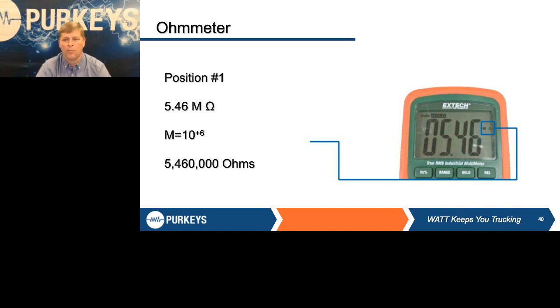So that is not 5.46 ohms, that is 5,460,000 ohms. Is that more than 6K? Yes. A lot of times those service manuals, all they're asking for is some sort of what they consider an infinite reading, or an open. So as long as it's at least 6,000 ohms, we consider that open and it's good. We're way above that, doesn't matter - that's what they're looking for, an open.